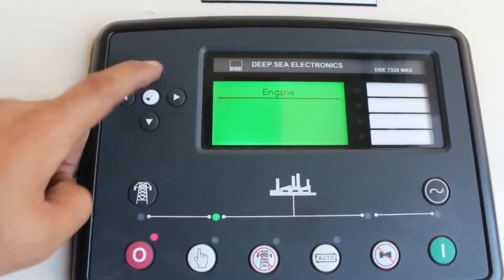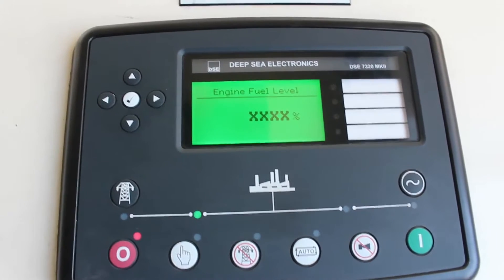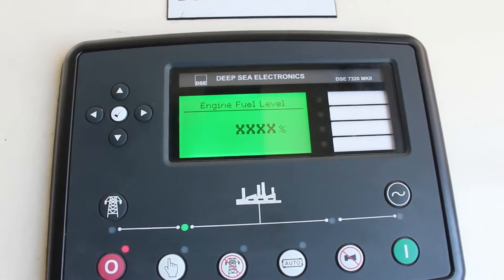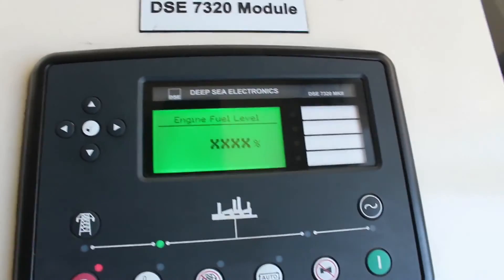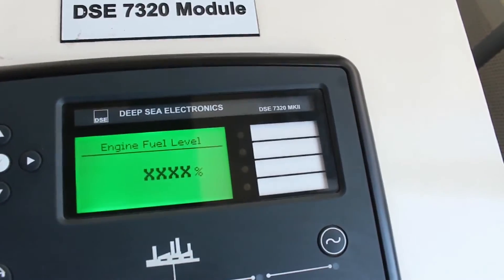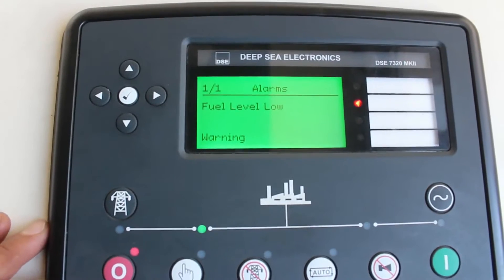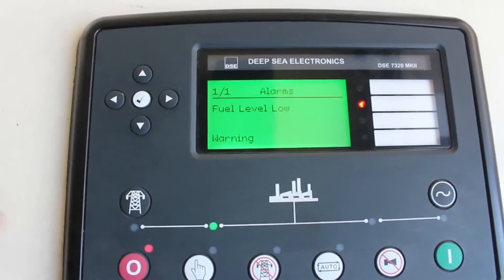You can see here the fuel. Since it is not yet connected to our module, the sensor is showing 'xxx' because there is no connection. Now I am going to connect so you can see what happens. Now you can see there is an alarm because there is no fuel, meaning it is giving you the feedback of 'fuel low'.